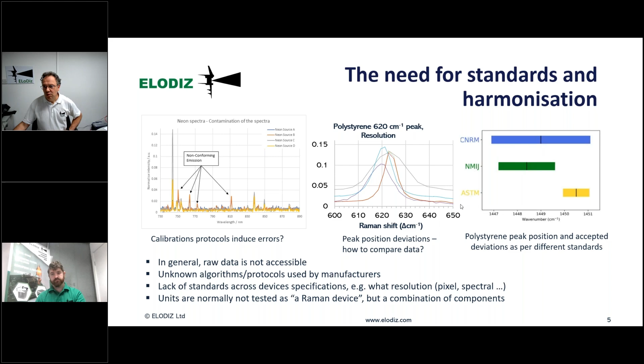It is perfectly observable. And then the most serious problem that we have observed is that some regulations, like pharmacopoeias, do not have standardized values that can be extrapolated across the different instrumentation. This is, for example, the case of the European pharmacopoeia, the Chinese pharmacopoeia, and the ASTM values that are used for the European and American pharmacopoeia. There is one particular peak in polystyrene, described by the ASTM and described by the Japanese pharmacopoeia. They don't overlap at all. So which one needs to be used?